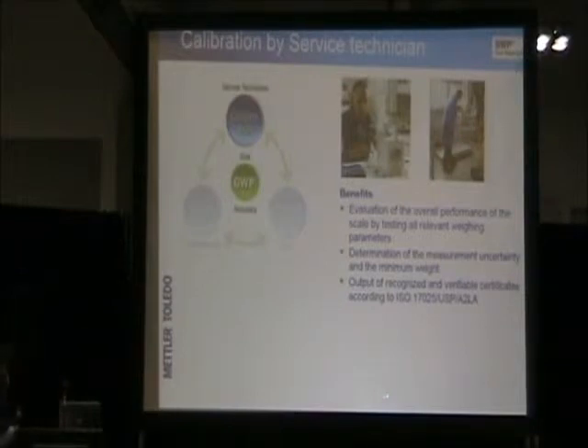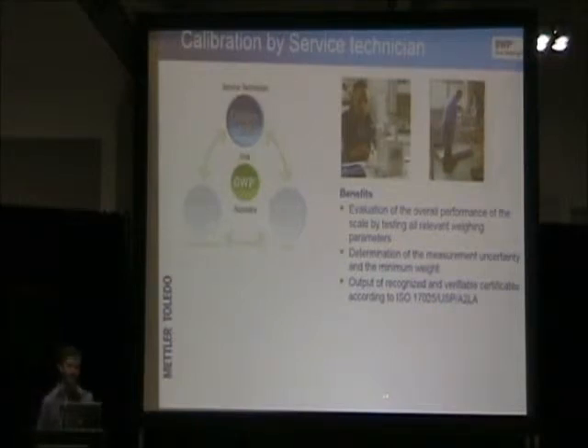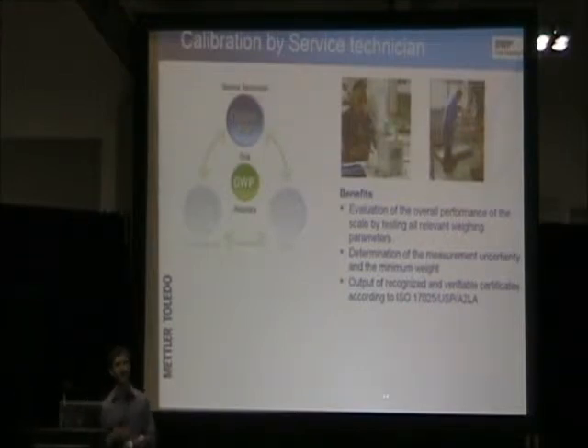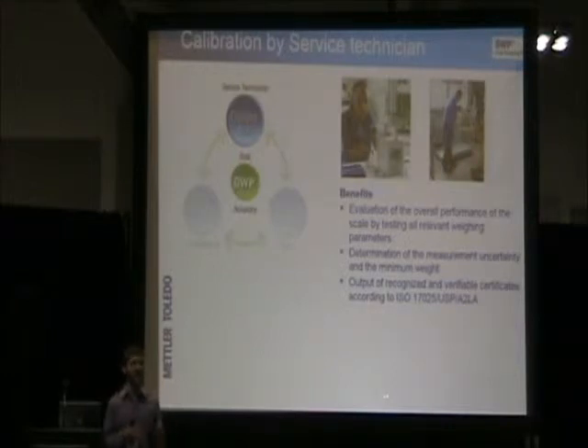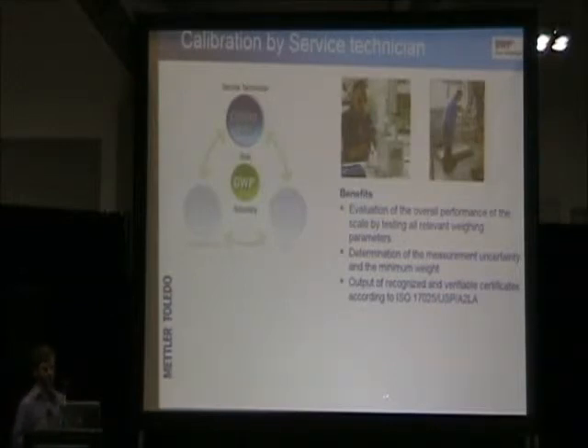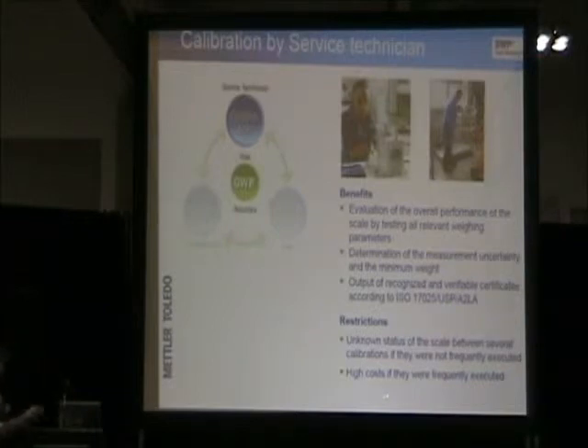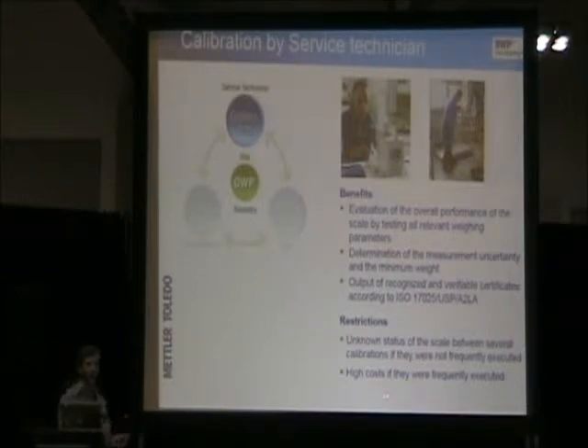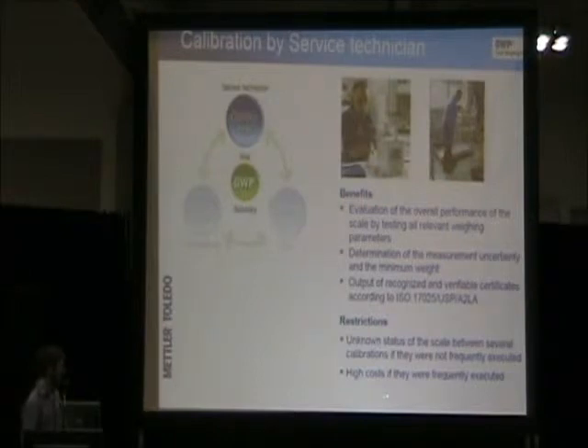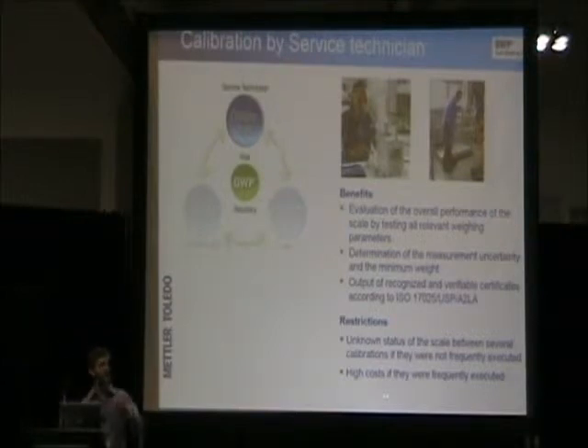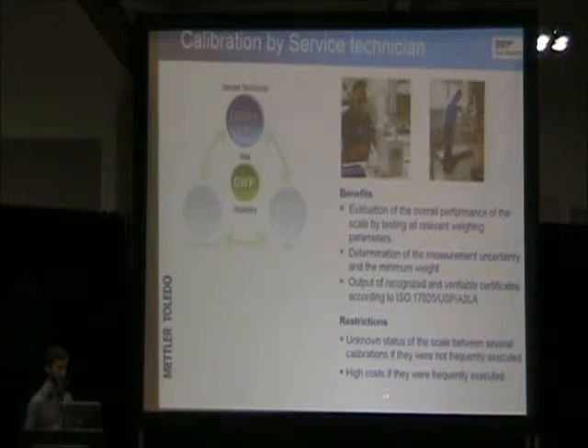So, calibration by a service technician. The benefit here is that you're going to have the overall performance of your instrumentation tested and figured out by a technician coming to your facility. You're able to determine the actual total uncertainty of measurement of your instrument itself, which will achieve the minimum weight. And you're able to get the necessary documentation to ensure that you're in compliance when an auditor comes. The restrictions here are that there's an unknown status of your scale from the time that the technician leaves your facility to the next time he's scheduled to come back in. And there's a high cost associated with that if they come to your facility more than they necessarily need to, or if you're trying to do testing on your own internally too often.